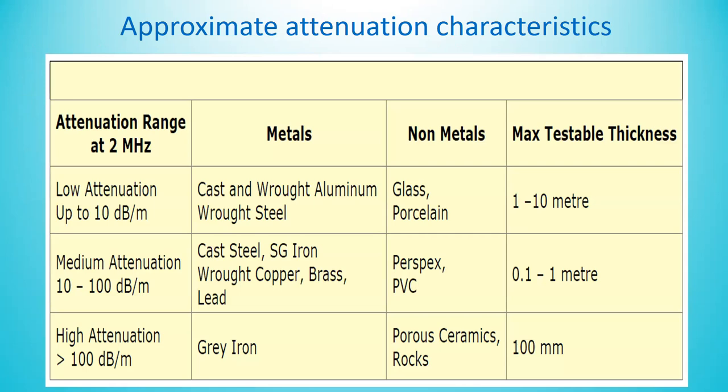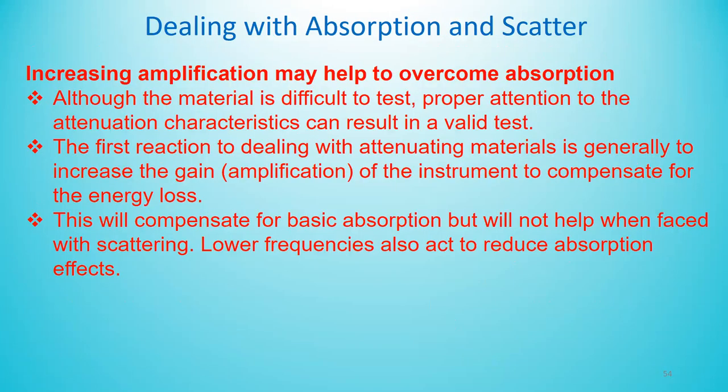So there are different materials, different attenuation. If you have more attenuation, you should rather go for low frequency. Increasing amplification may help to overcome absorption. Although the material is difficult to test, proper attention to the attenuation characteristics can result in a valid test.